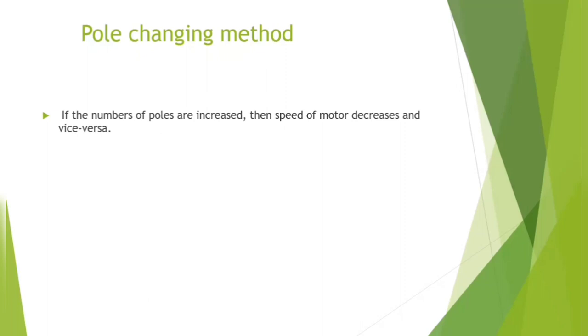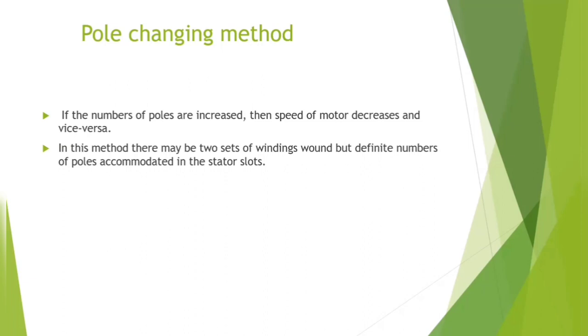They are inversely proportional. Higher the number of poles, lower will be the speed of the motor. In this method, there may be two sets of winding wound with definite numbers of poles accommodated in the stator slots. We choose the motor having two RPM ratings for the pole changing method.